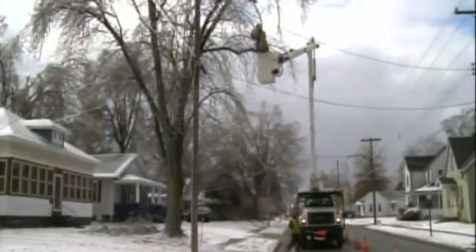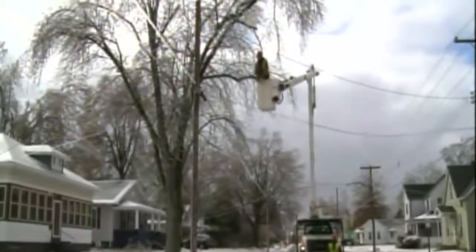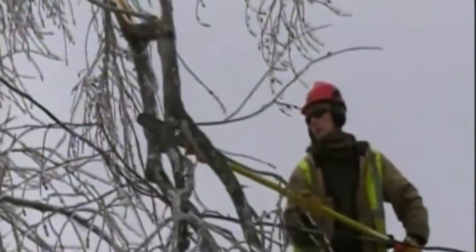What we expect is individual events, which we manage from our control room here. Then they start increasing in frequency, and we build from individual events to what we call feeder outages, perhaps substation outages. If we start losing transmission capacity, then we'll be into what's called rotational load shedding, where we actually have, in common terms, what most people call rolling blackouts.